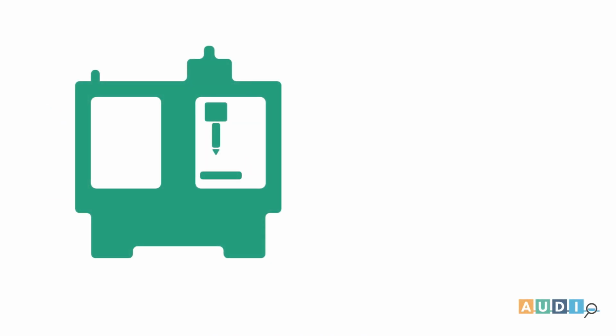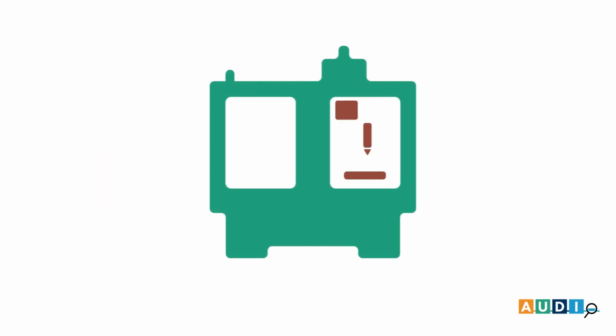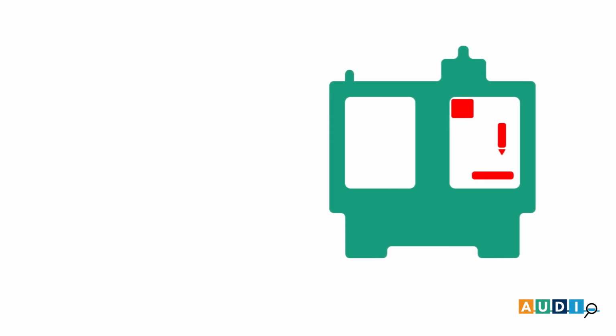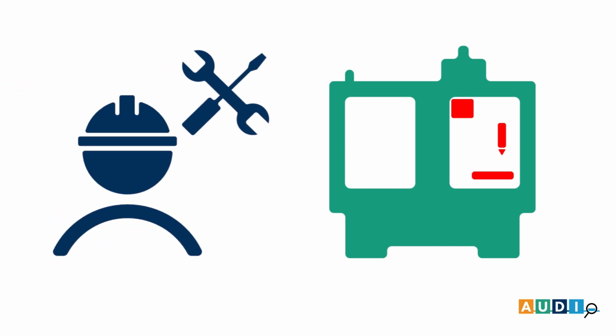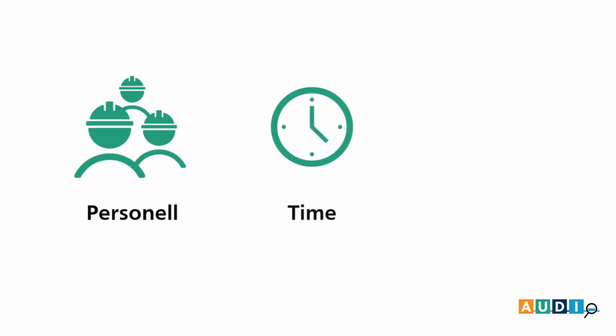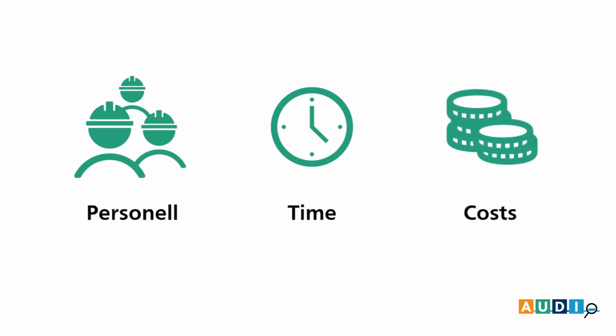During their service life, machine tools must be calibrated regularly in order to meet the accuracy requirements of modern manufacturing. For this purpose, trained personnel of the machine manufacturer must travel to the installation site of the machine several times a year, depending on the machine type and area of application, and carry out the corresponding work. Such procedures are associated with enormous personnel, time, and monetary expenditure.